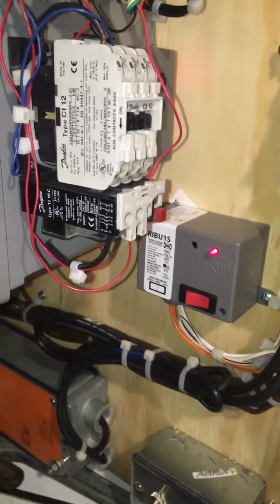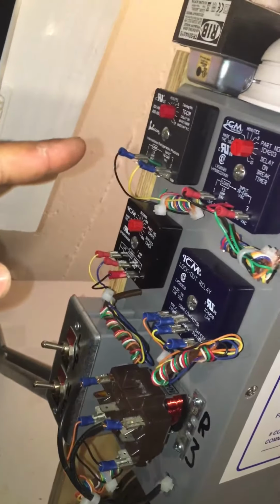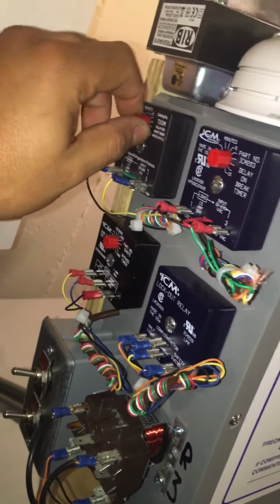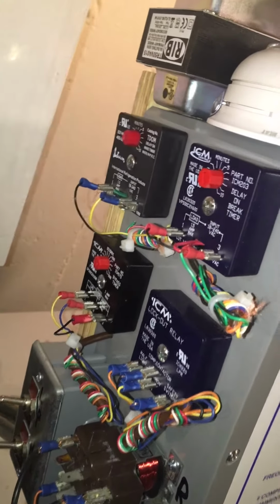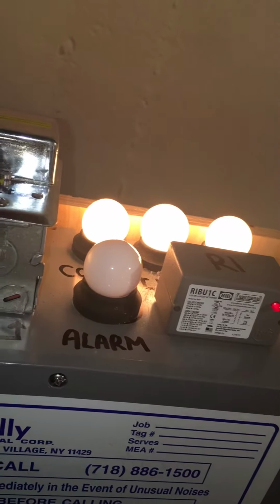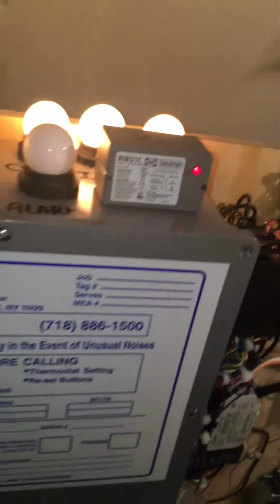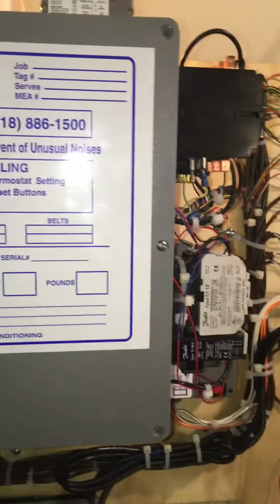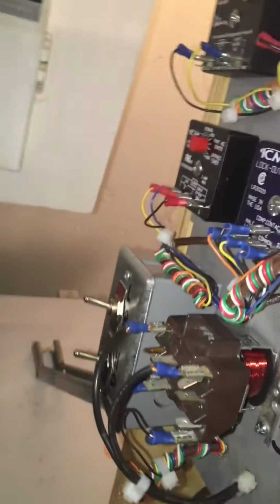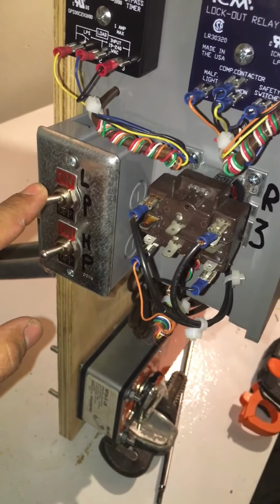Now we're calling for cooling. Cooling has not been yet initiated by the compressor due to time delay on make timer. So just to speed things up, we'll crank that back down. There that goes. Compressor, fan, and pump is all running right now. Now we simulate low pressure bypass timer play. Put the delay on it. I open the low pressure switch.